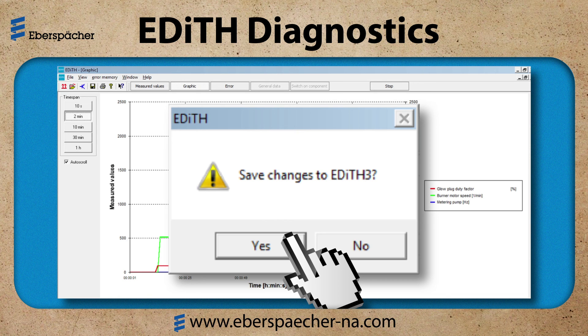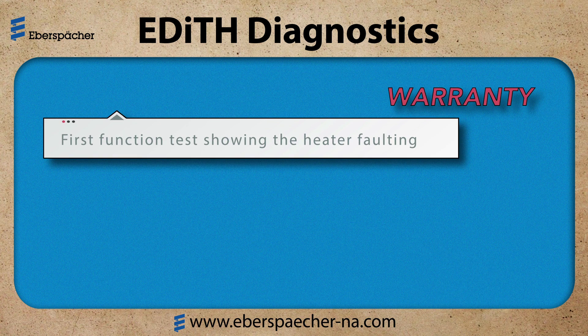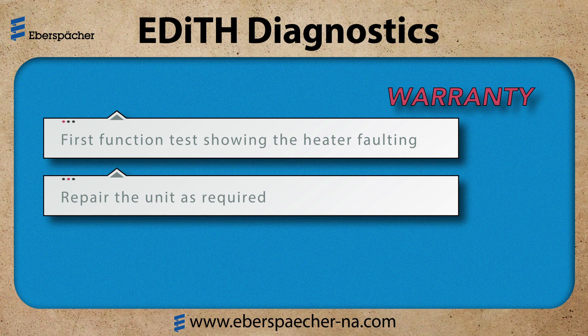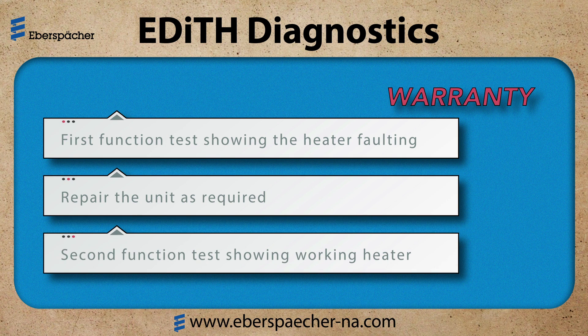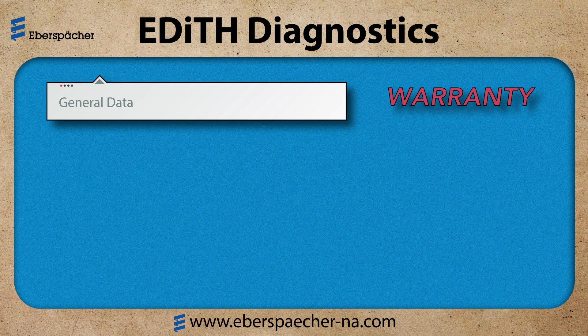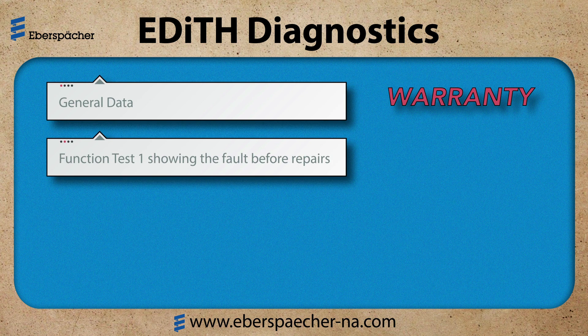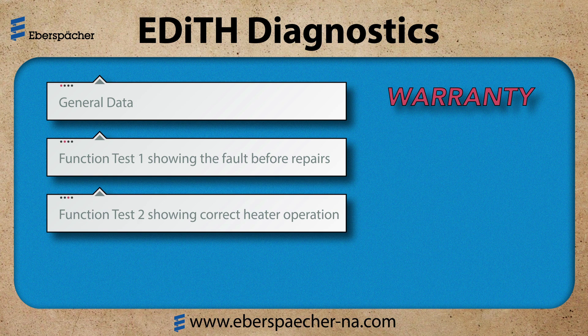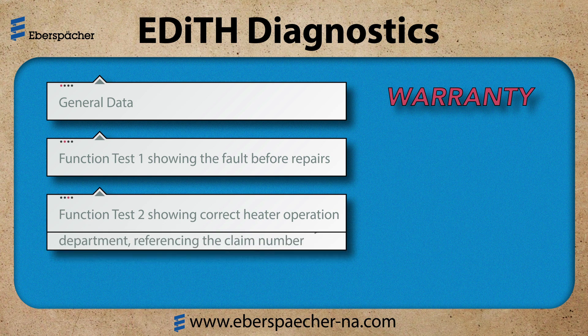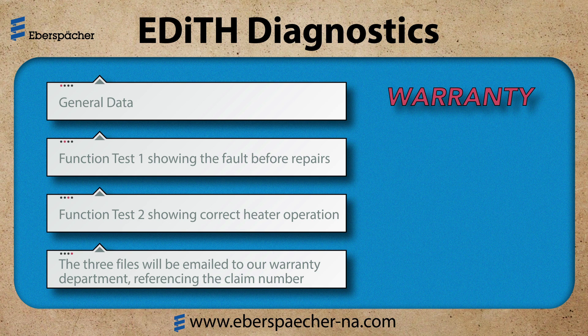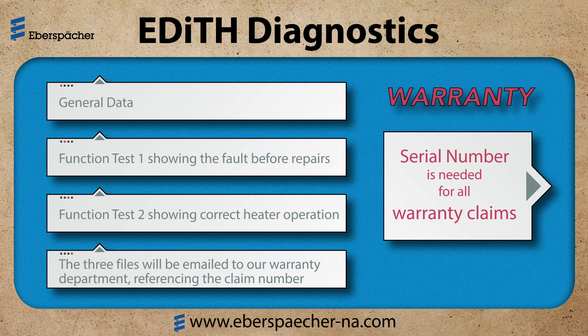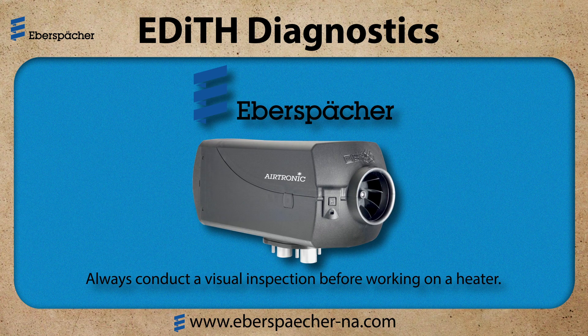If this is a warranty case, I need to save the test. I should have the first function test showing the heater faulting. I will make the repair as required and then complete a second function test. The test saves needed for warranty are General Data, Function Test 1 showing the fault before repairs, and Function Test 2 showing the correct heater operation. The three files will be emailed to our warranty department referencing the claim number. Remember, the serial number is needed for all warranty. Always conduct a visual inspection before working on a heater. Thank you.